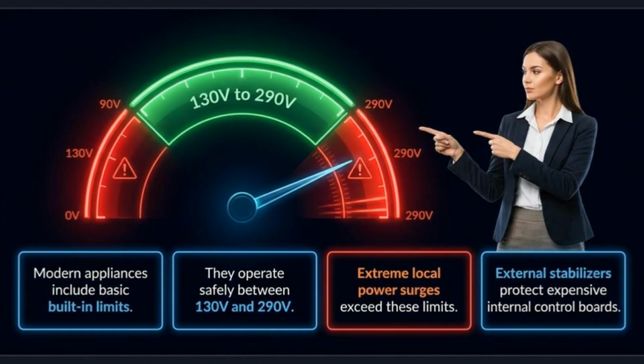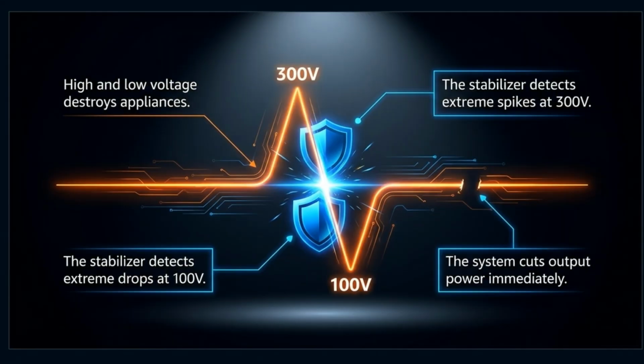Modern appliances have basic built-in limits, safely operating between 130 volts and 290 V. External stabilizers protect internal control boards from extreme local power surges that exceed these limits. Extreme voltage, both high and low, destroys appliances. The stabilizer detects extreme spikes at 300 volts and drops at 100 volts. The system cuts output power immediately in these situations.